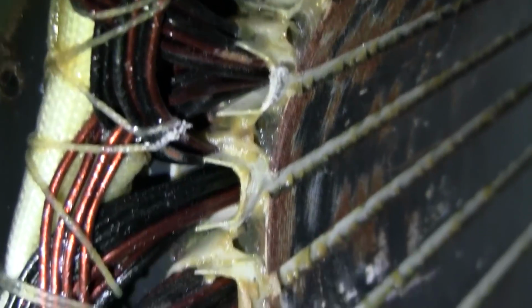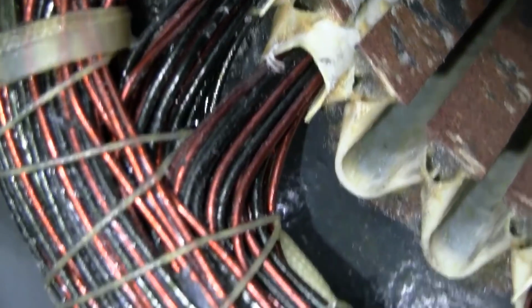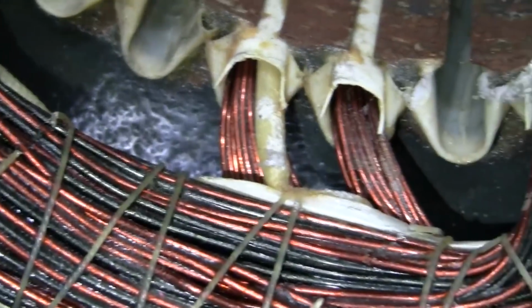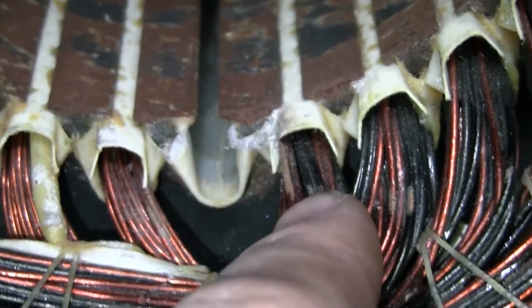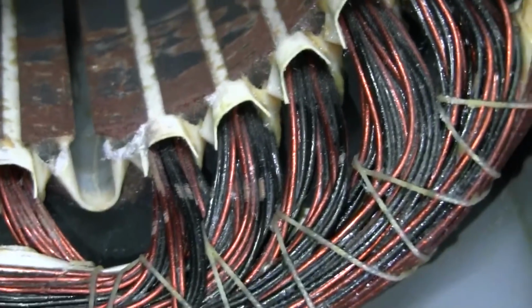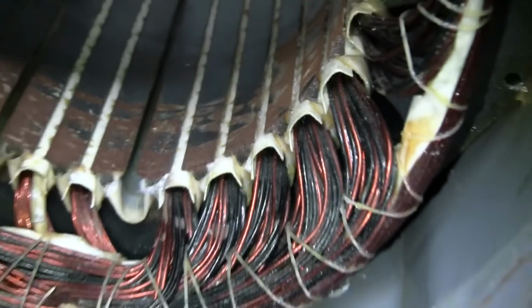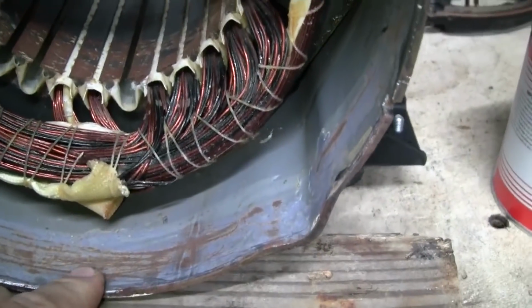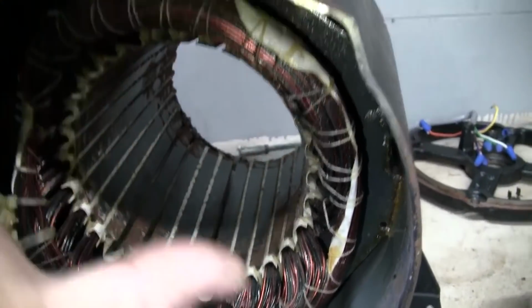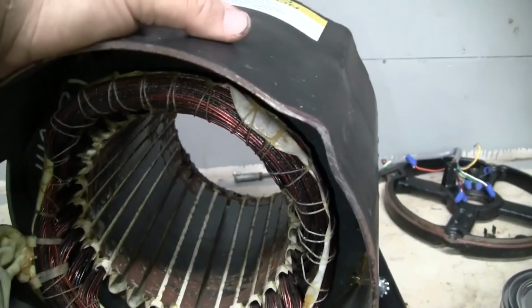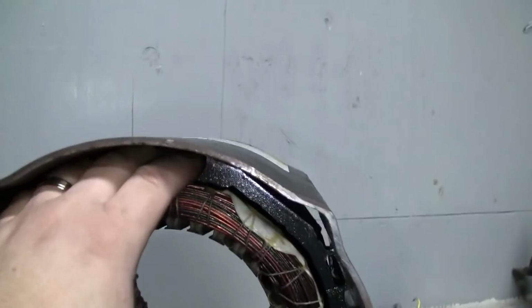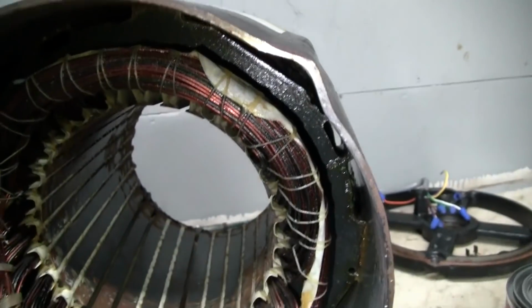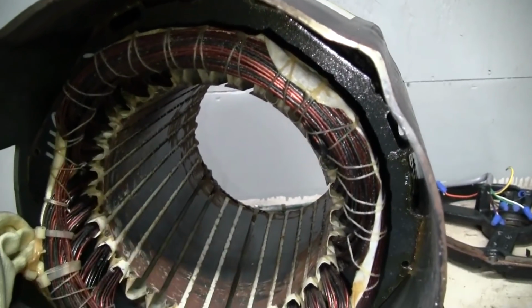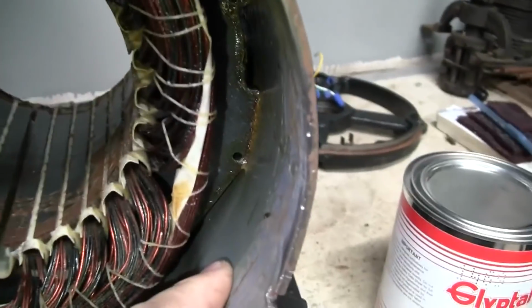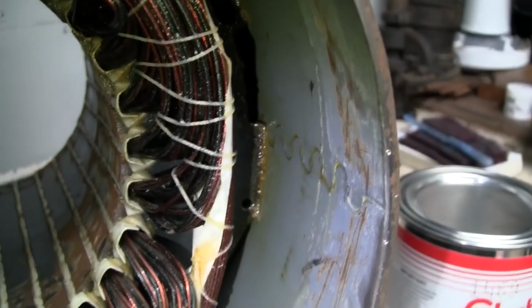Right there. A couple others. But this is by far the worst area, right in here. But I have a theory about this, and I think it was done at the factory. What I'm noticing is that this whole stator, the whole assembly here, the frame, the armature, or the lamination and the windings were assembled and dipped in a varnish, because the varnish is on the inside of this housing here, and it was baked.